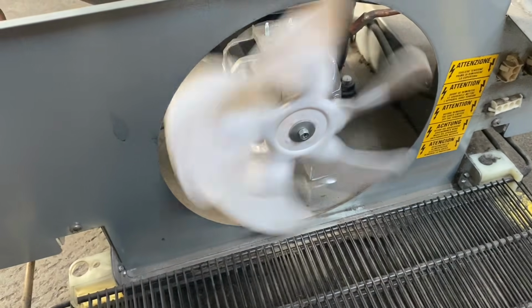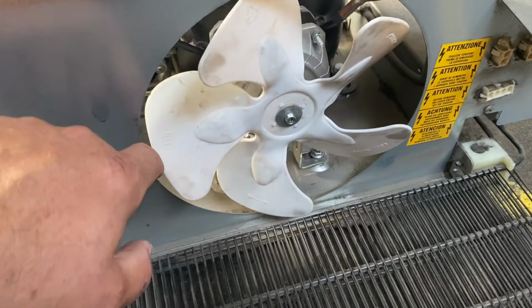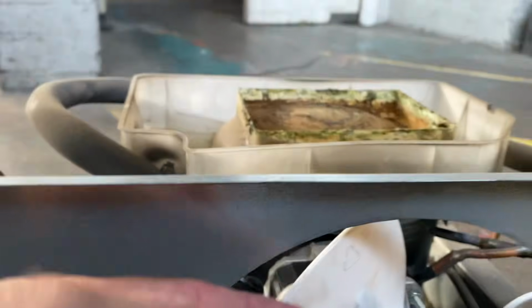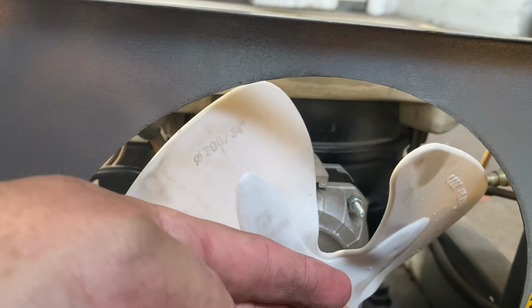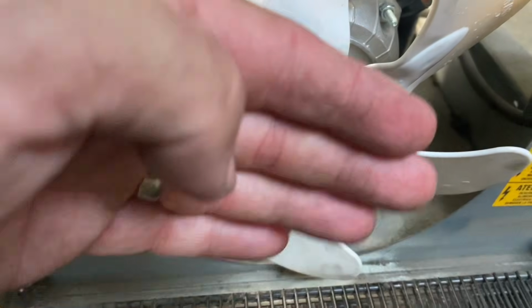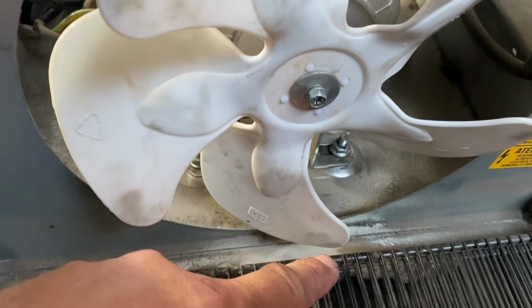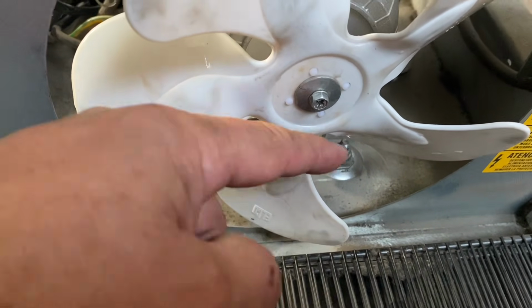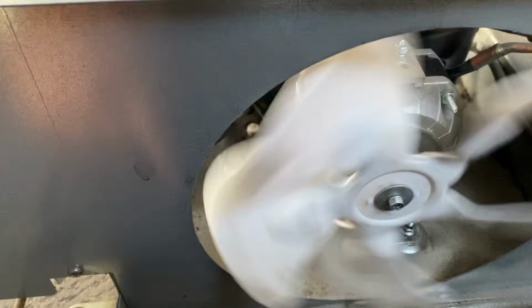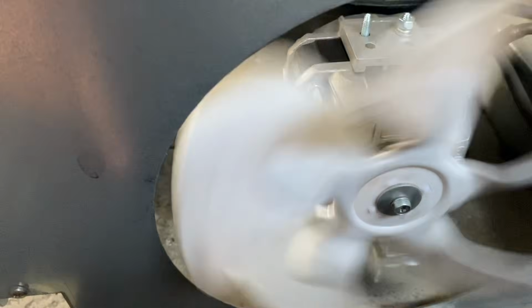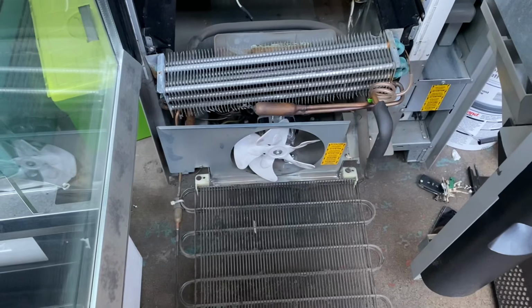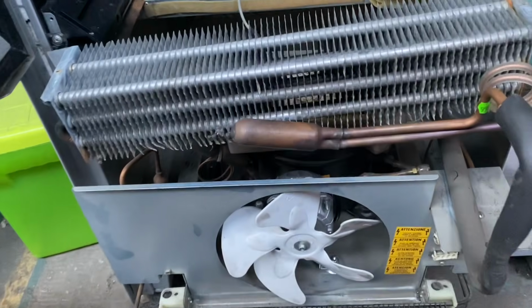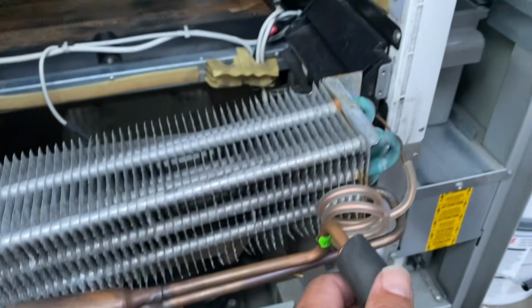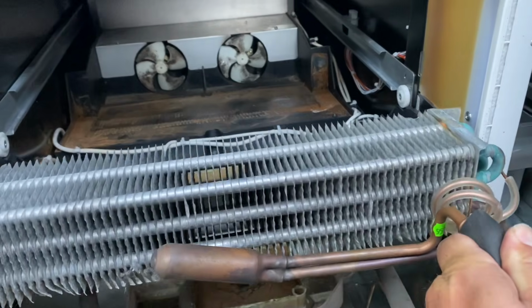If that fan motor's not housed correctly or it's slightly out of line, then sometimes you get the fan hitting the side of the chiller unit, which causes a big clicking sound when the fan motor's spinning. So just make sure that it spins freely. If it doesn't, there is a little adjustment on there. You can move the bracket of the fan motor left and right, forwards and backwards, so you can get that sorted. Okay, now we're ready to put it back in.